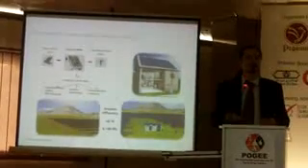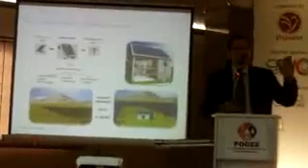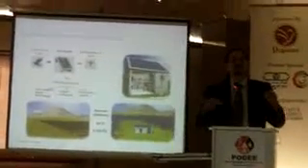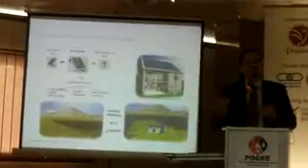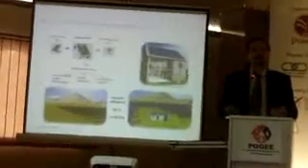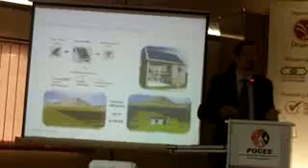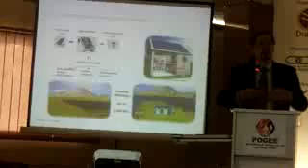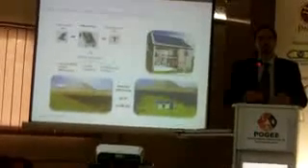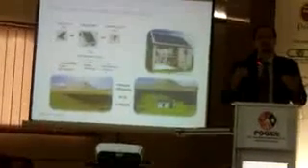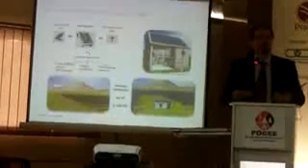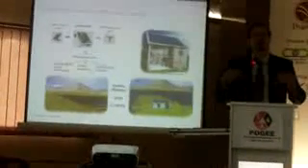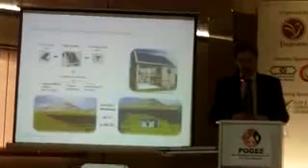The utilities are sending us ripples, controlling our plants or the plants of operators in active power, changing statically or dynamically reactive power, and the inverters and the whole PV plant are required to participate in the grid management, to stabilize the grid and also to support the grid in moments when the grid is very weak. So these are all new features that the inverters have already, and important if you have large amounts of PV that you integrate into the grid.